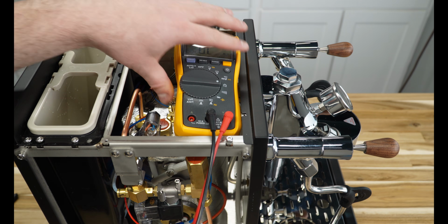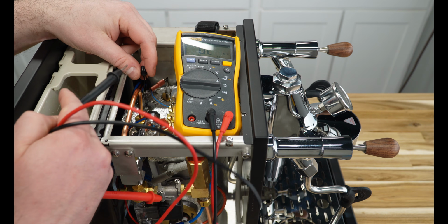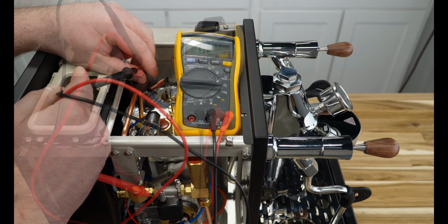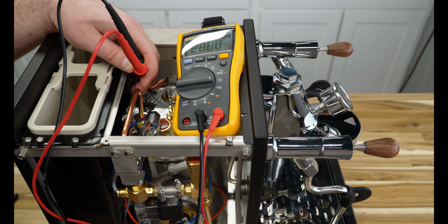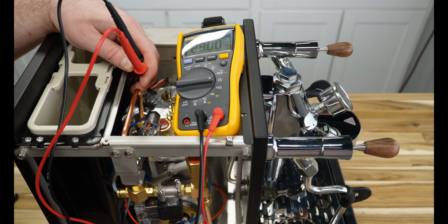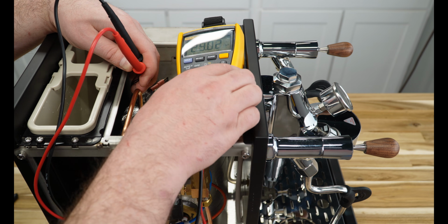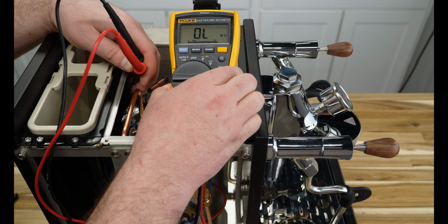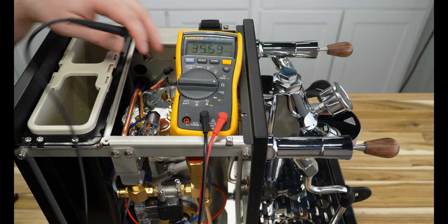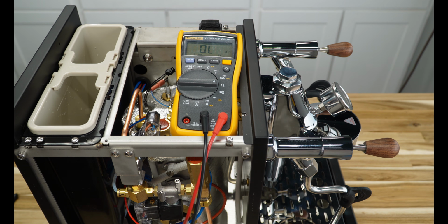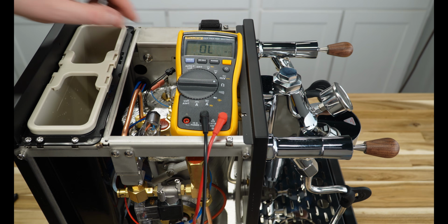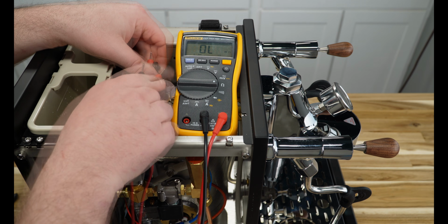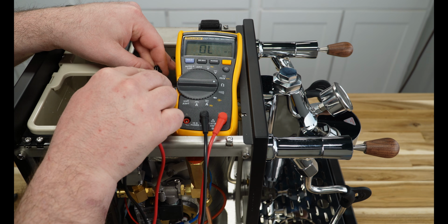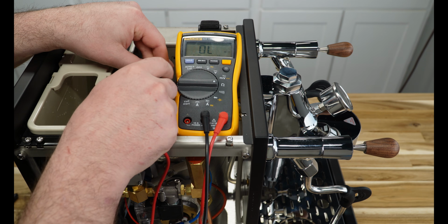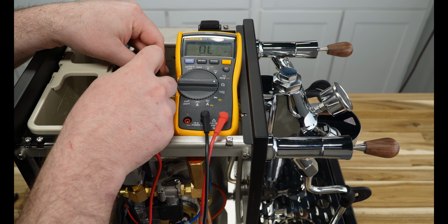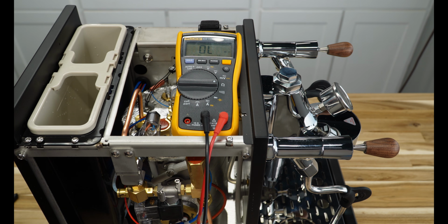So I'm going to take this. It's going to be a little awkward to reach in there. So we have 29 kilo ohms. It's a very high reading. That's something that we would be happy with seeing. If it was something like 10 ohms, that would tell us it's probably going to the body of the machine, or if we touched it, and you really kind of have to dig in there to make sure that they connect. But if we had that OL, we would know that probably one of these wires is broken and this probe is bad.